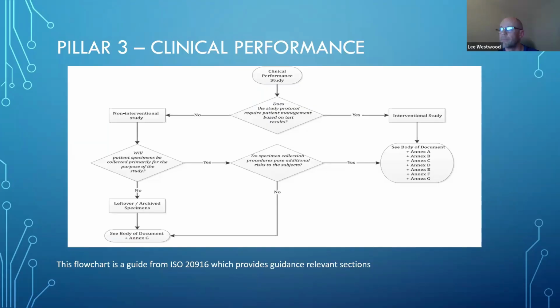So from this flow chart here, you can see which elements of ISO 20916 apply to your study's type. So you can see if you have an interventional study, all those annexes apply, and you have to comply with all those annexes. Whereas if you have leftover samples and there are no patients involved, it's far more straightforward. So keep that in mind when you're documenting your studies. And 20916 has all the requirements for study planning, ethical approvals, document requirements, reporting requirements, study monitoring, everything that you need to run a study in the European Union is covered in ISO 20916 and in those articles I just mentioned before.